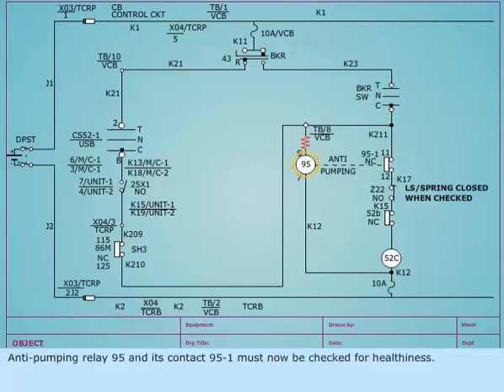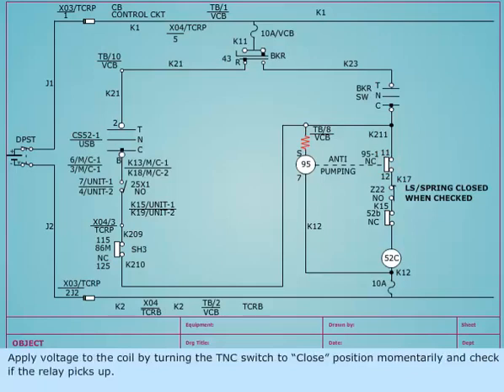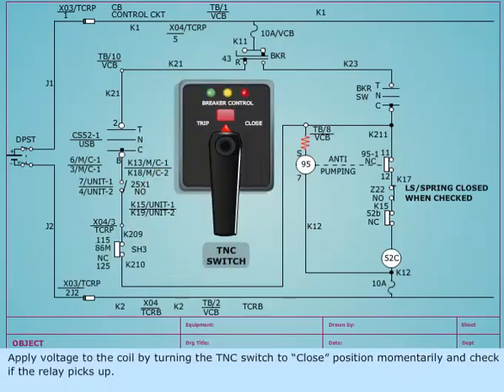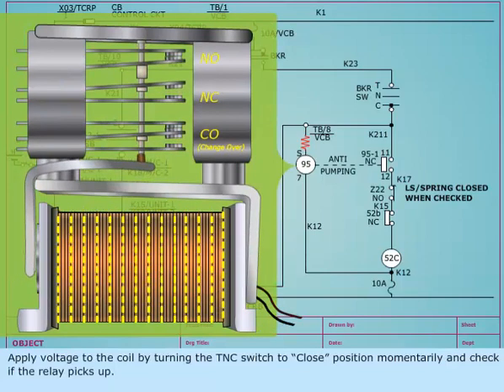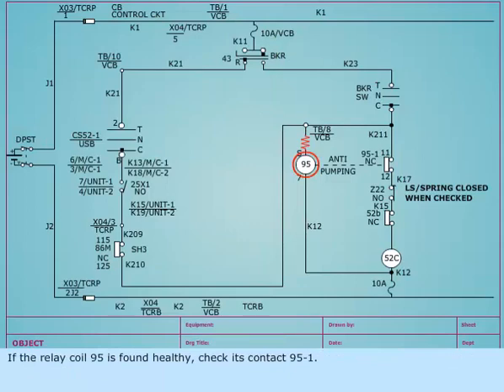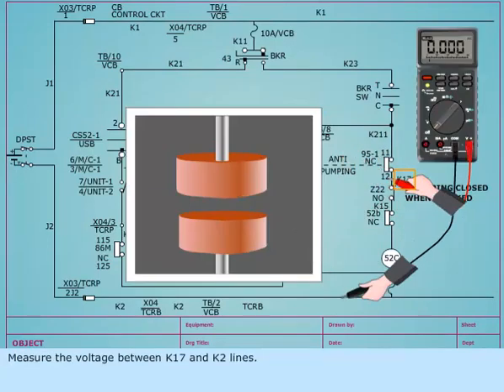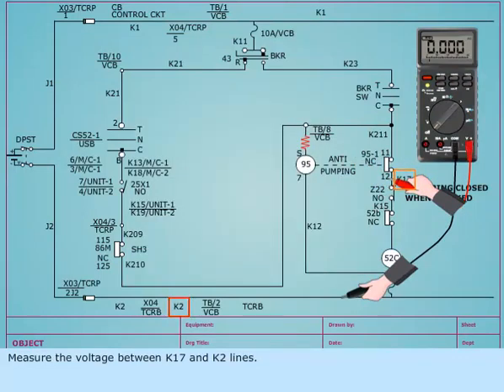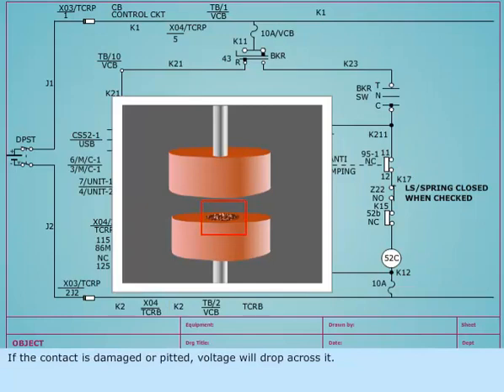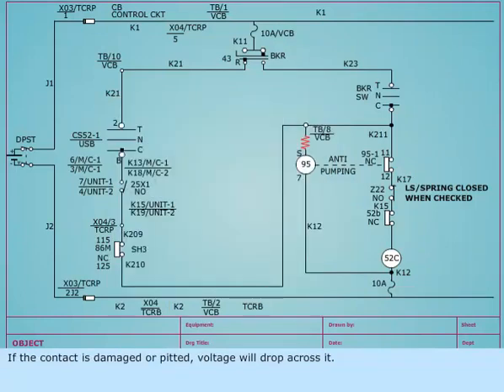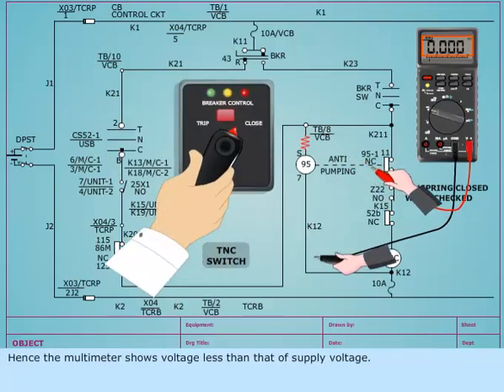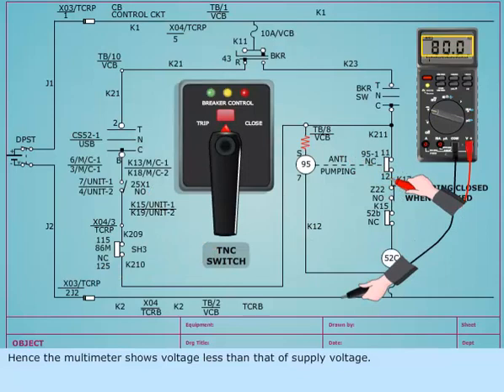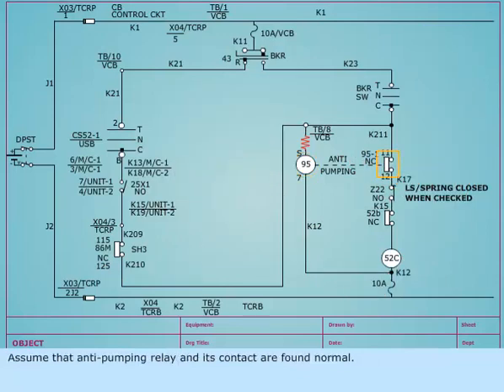Anti-pumping relay 95 and its contact 95-1 must now be checked for healthiness. Apply voltage to the coil by turning the TNC switch to close position momentarily and check if the relay picks up. If the relay coil 95 is found healthy, check its contact 95-1. Measure the voltage between K17 and K12 lines. If the contact is damaged or pitted, voltage will drop across it. Hence, the multimeter shows voltage less than that of supply voltage. Assume that anti-pumping relay and its contact are found normal.